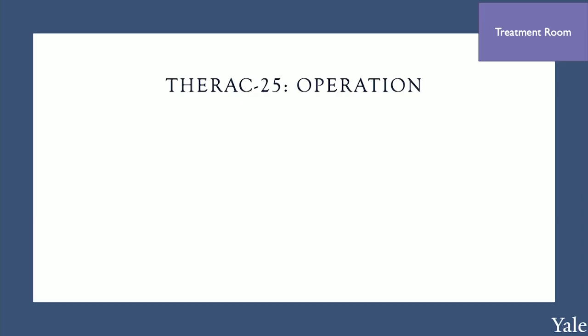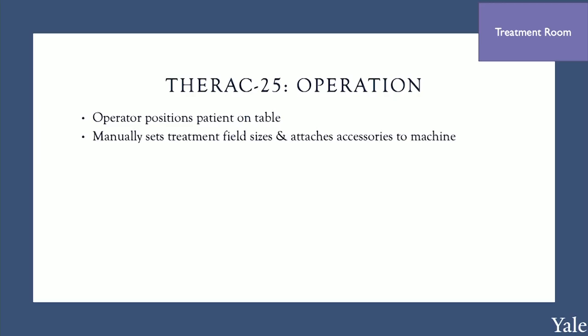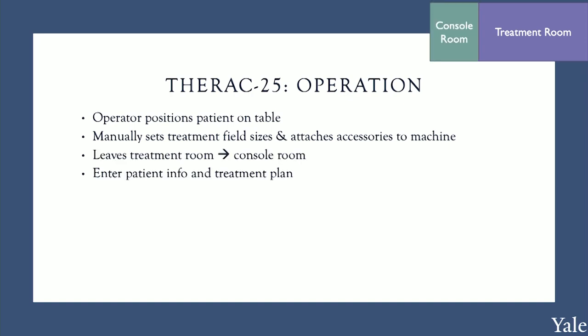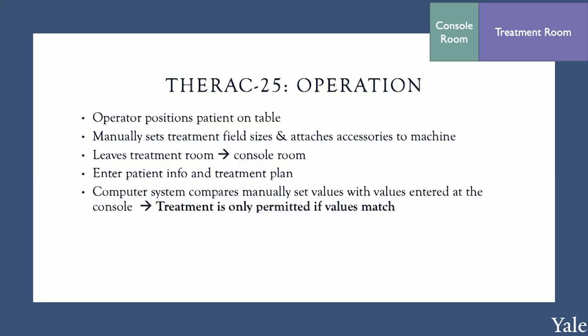Let's walk through an operator's interaction with the software. The operator first positions the patient on the table in the treatment room, then manually sets the treatment field sizes and attaches the necessary accessories to the machine. The operator then leaves the room and controls everything from a console room. The patient's info and treatment plan are entered into the software system, and the computer checks to make sure the manually set values match the values typed into the console. If the values match, treatment begins. Operators began complaining that it was redundant and time-consuming to re-enter the data, so the Atomic Energy of Canada Limited, or AECL, modified the software to copy treatment data from the manually set values.